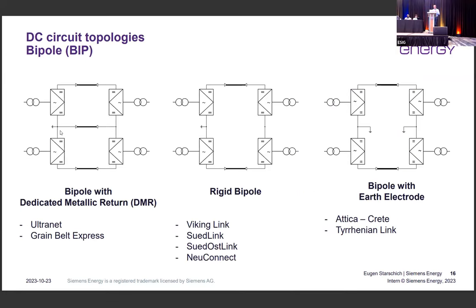So what is the other configuration, the rigid bipole? The bipolar configuration is born of the idea that we need a little more redundancy in the system. So I will build a system consisting of four HVDC converters and three conductors. This is called a bipole with dedicated metallic return, DMR, which means a three conductor setup. There are projects like Ultranet and Grain Belt Express which use three conductor technology.